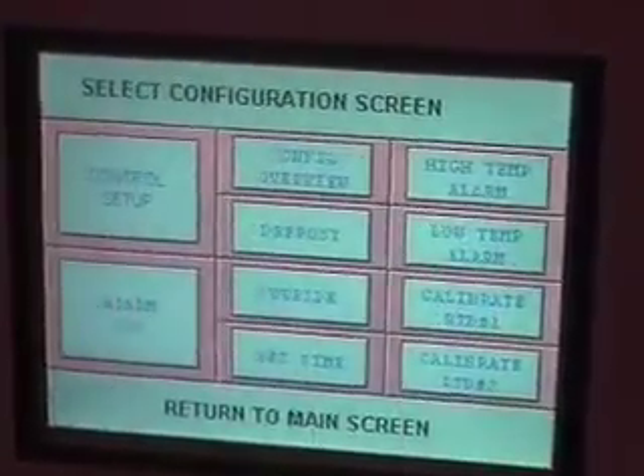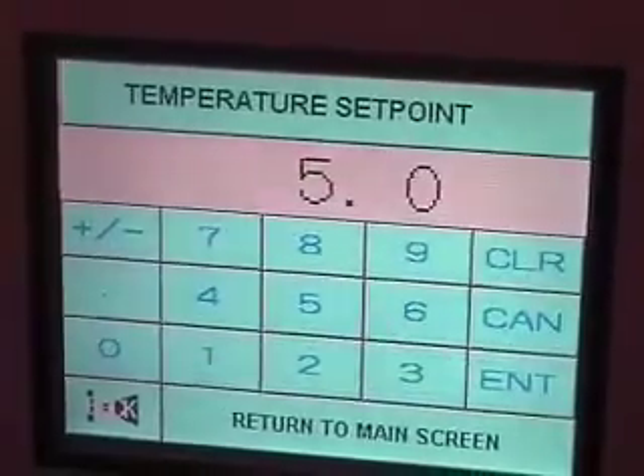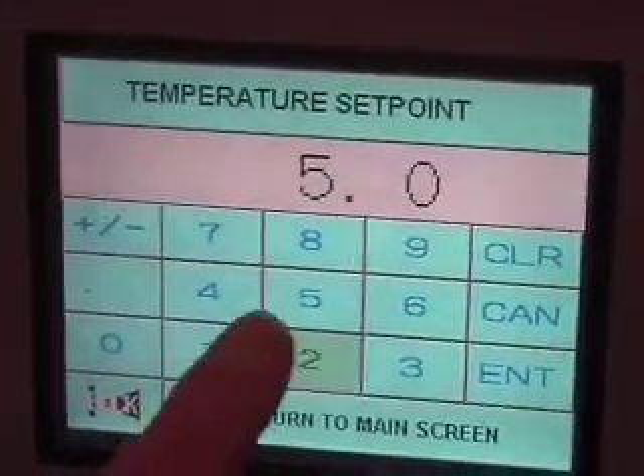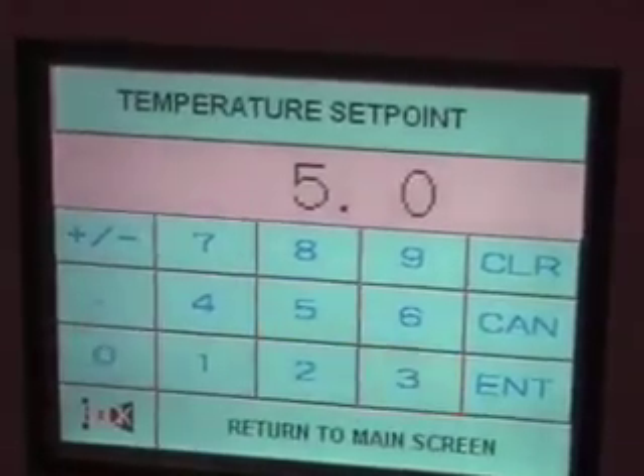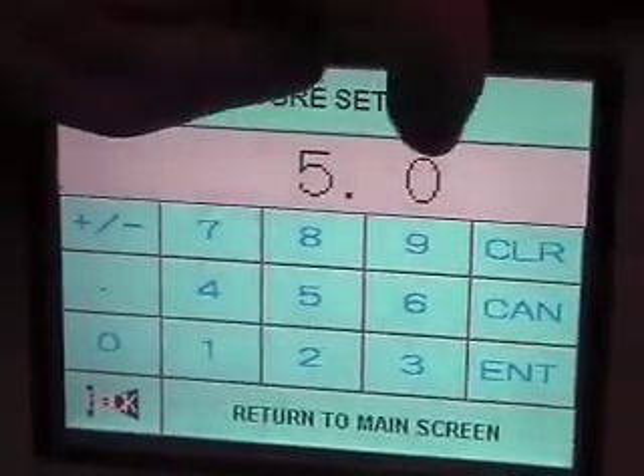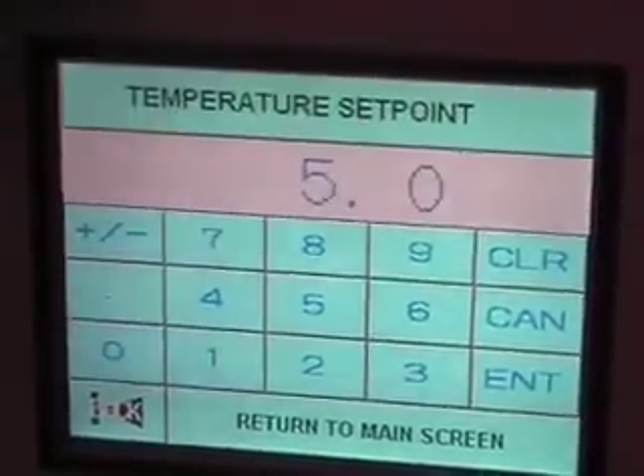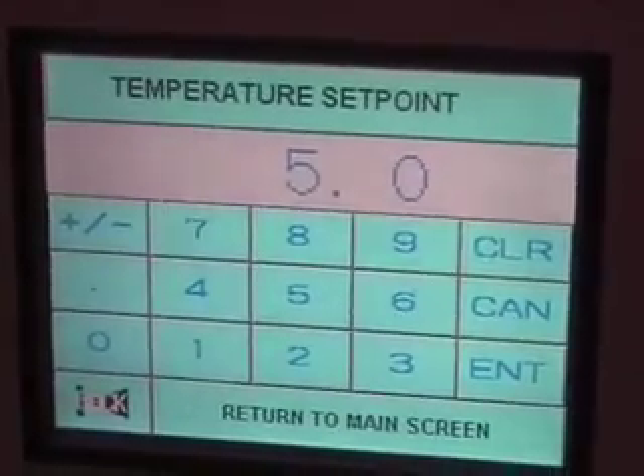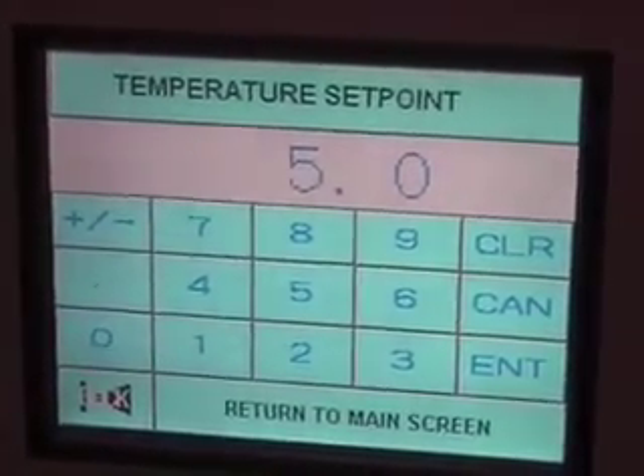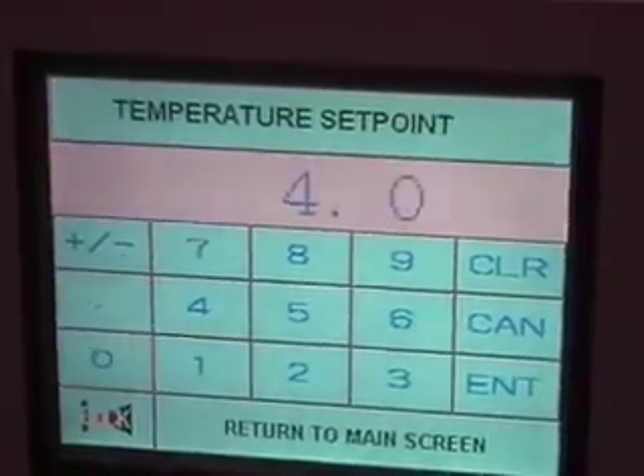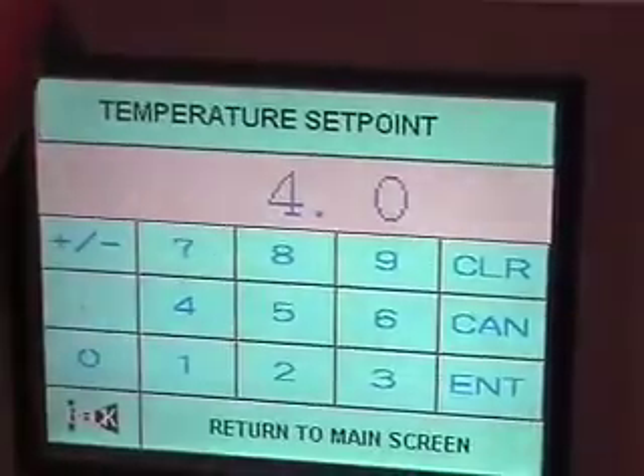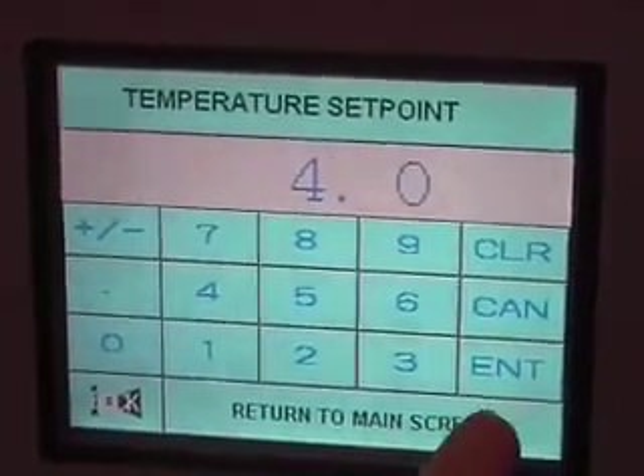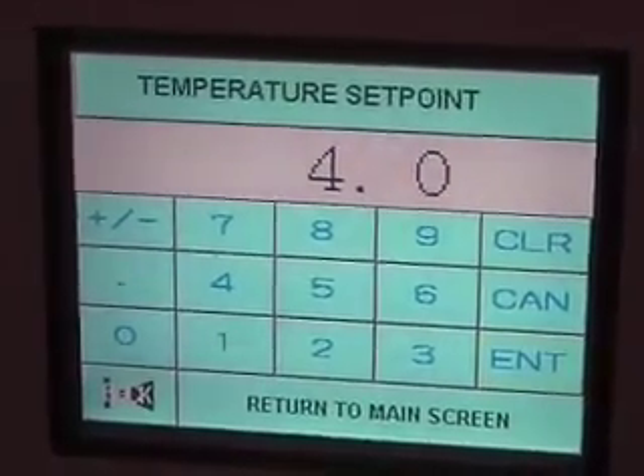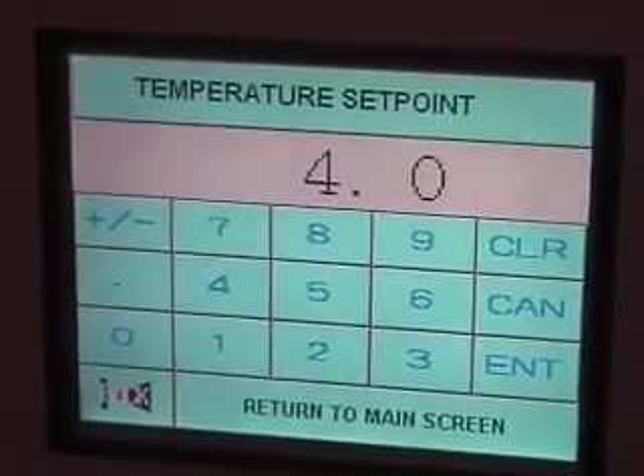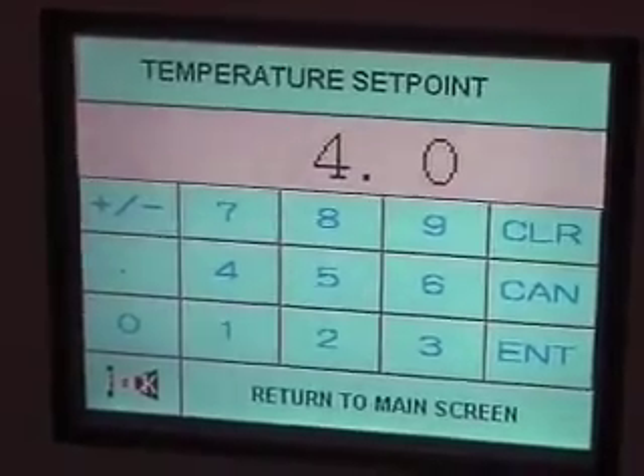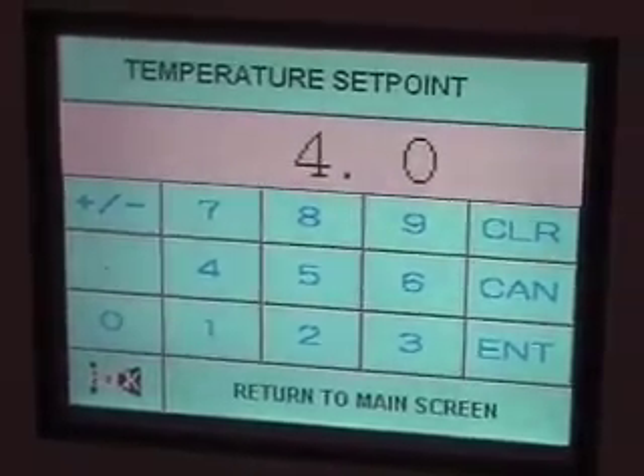Let me go over that so you can tell. Most screens are going to change this way. You can touch buttons all day long, nothing happens. You have to activate the number, and you do that by pressing it. You notice it turns blue. That means it's now a volatile number, so it can be changed. You make it 4.0, and still nothing's happened. You have to enter that into the memory. Boom, it turns back to black. That is now the value of your set point. Okay. Almost all screens are going to be that way.